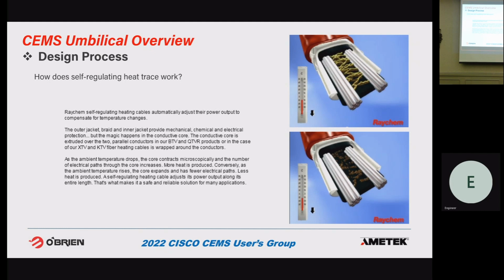So you electrify, put electricity across the two bus wires, and the electricity is looking for a path of least resistance. So what it does, it sees a piece of carbon black, and it essentially jumps or arcs to it, and then to the next one, until it reaches the other bus wire. So it's an electric chain that it produces. And as it's making those jumps, there's resistance. That resistance produces heat. So you get a bunch of these electrical chains happening all down the length of the tracer. So that produces heat, tracer starts heating up.